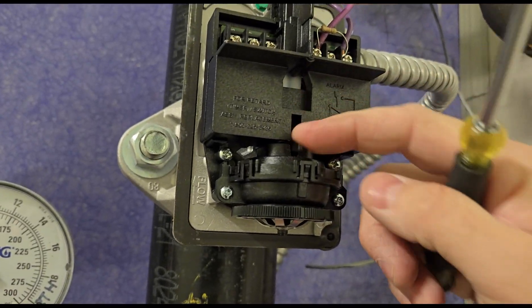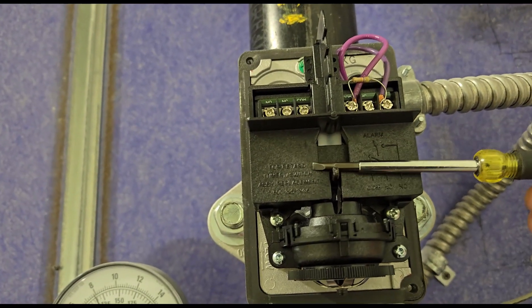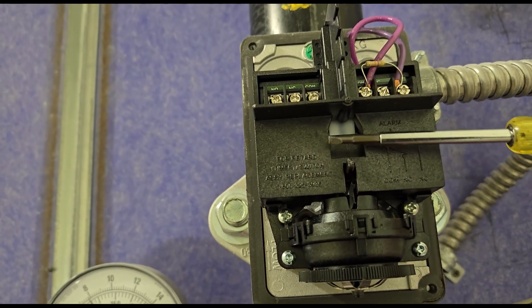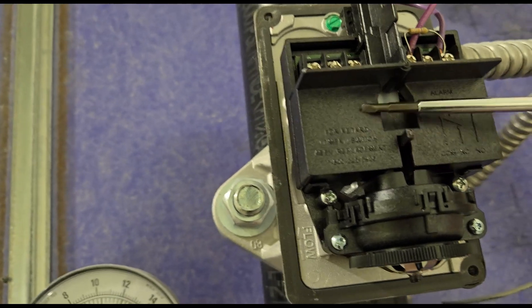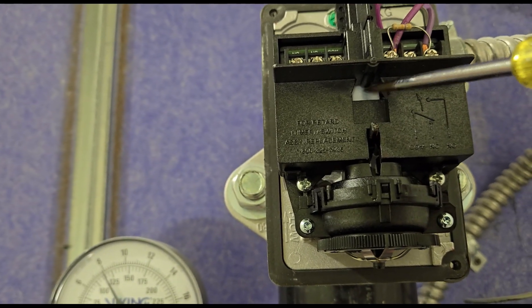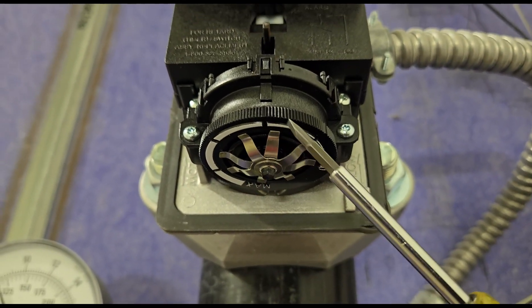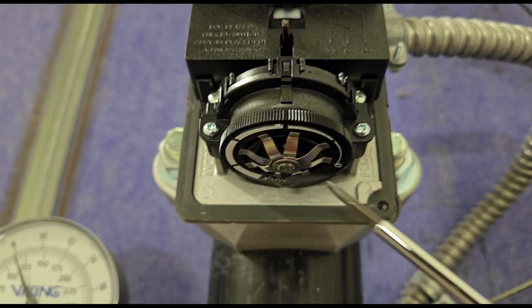So I could manually do it, of course, but we're going to do it with our flow. So again, we have our wiring up here with our resistor, our little lever, which is attached to the flapper on the inside of the pipe. When the lever gets down, the timer starts. We wait for this white plunger to drop. When it drops, it activates. And we can adjust the timer with the turn dial right here.